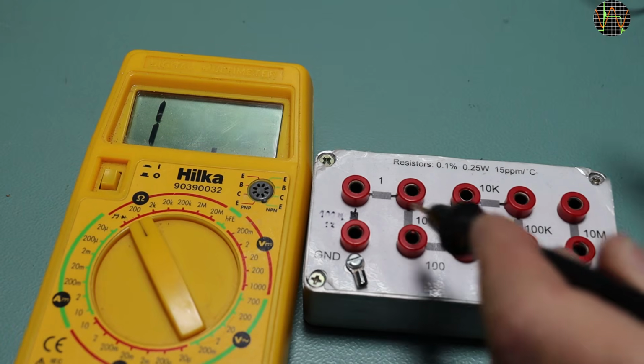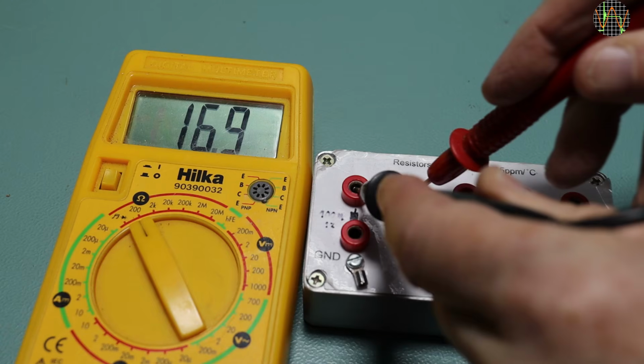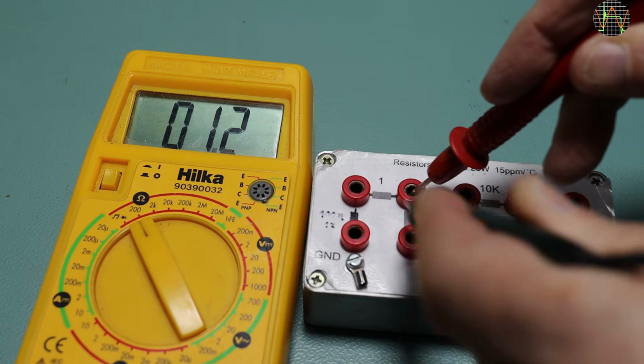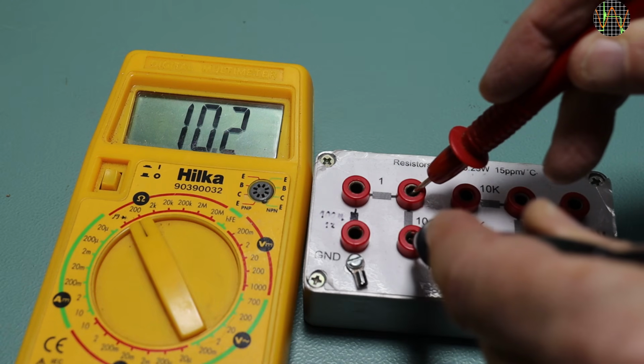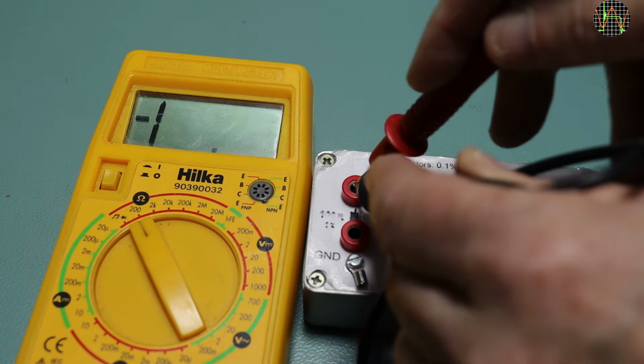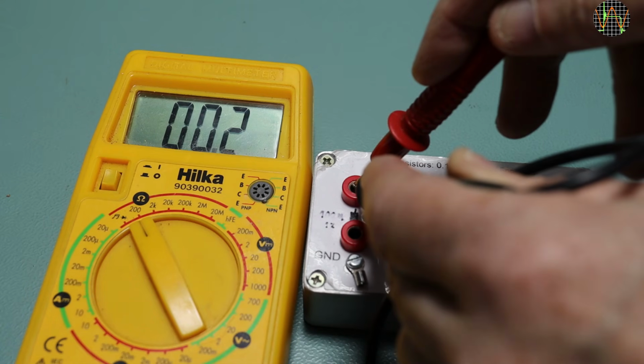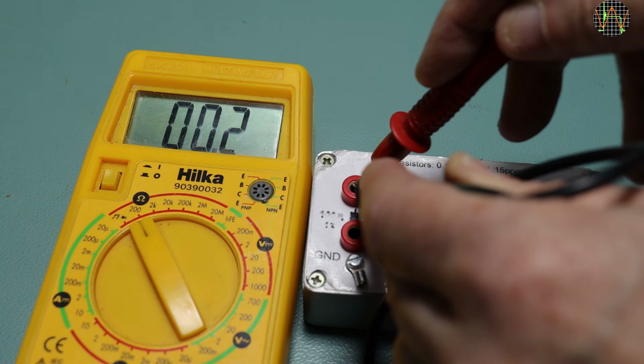Let's measure resistance the same way I did for the Schneider. 1 ohm and the Hilka says 1.2. For 10 ohm it says 10.2. That probably means the lead resistance is 0.2, which it is indeed. Since there is no rel mode, you have to mentally subtract that from the measurements.